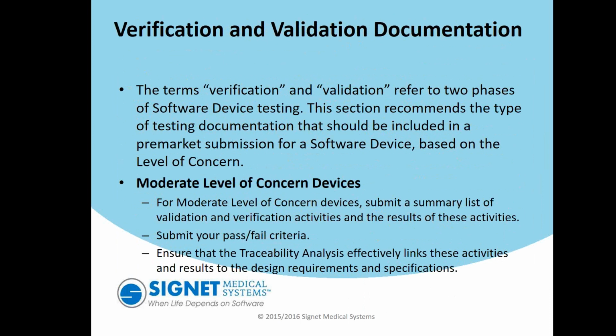Algorithm testing is certainly a part of verification and validation, and certainly a part of clinical analysis. You want to make sure your algorithms are performing correctly. Say that you're delivering a particular amount of fluid. You want to make sure your algorithms are definitely delivering that amount of fluid.